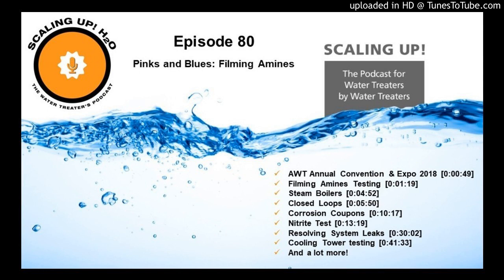That being said, we went ahead and put the 750 ppm dose in after we flushed that system, and we let that go for about 2 weeks. When we came back, that nice clear water that we left the system with was now tinted black. Now, it wasn't black, you could still see through it.